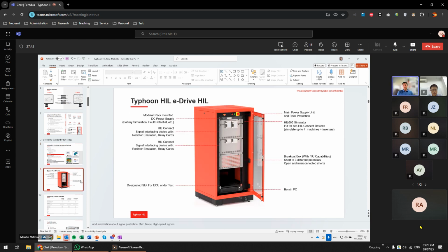On the topic of what a typical eDrive solution looks like, this is it. It comes in an industrial grade rack, and I'll name some of the components starting top to bottom. On top you have the main power supply unit. Below it is our DC power supply, used to power the DUT and provide potential lines for battery voltage and fault potentials that can later be inserted through the fault insertion unit into your DUT and circuitry, so you can test your devices' and software's reactions to the faults.